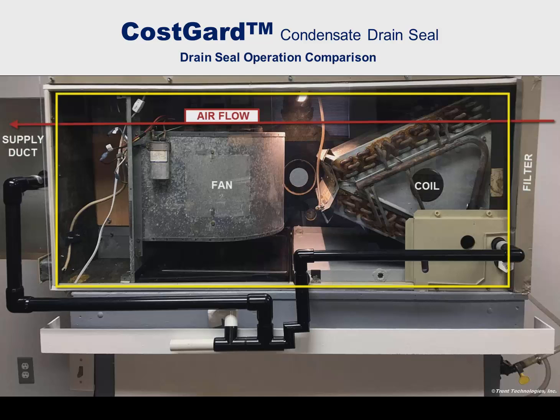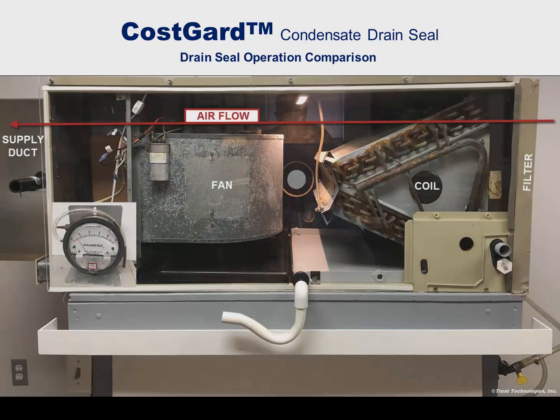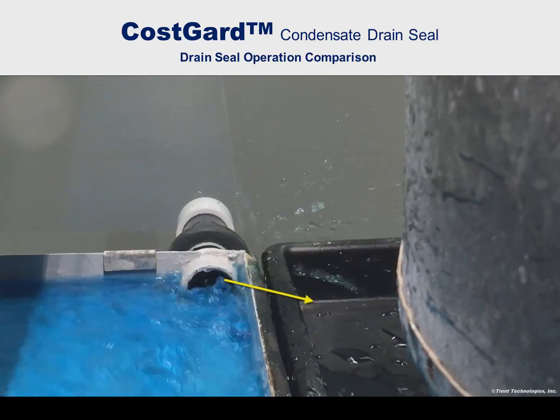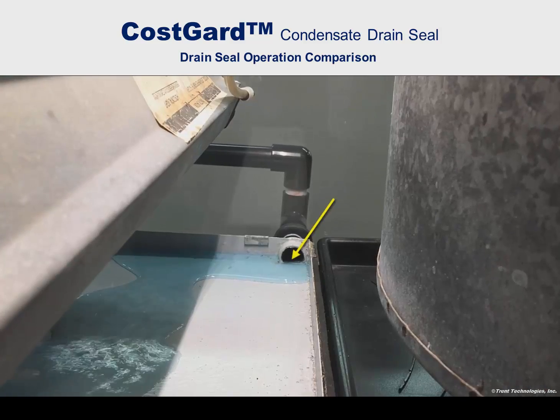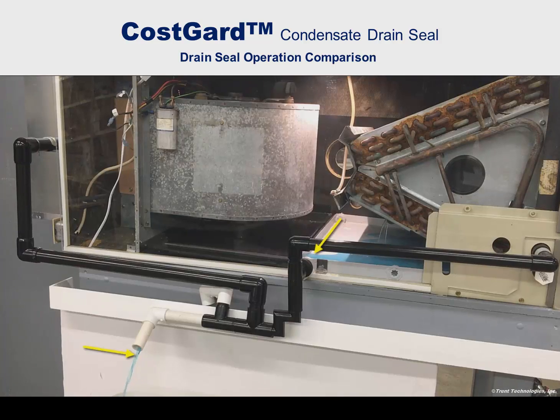With the aid of front and rear transparent panels, the effectiveness of the CostGard condensate drain seal system in preventing the blowing of condensate in a small fan coil unit operating at negative 0.6 inches of water column versus a trap is shown here. See the ingestion of air through the empty trap as the drain pan fills and the blowing of condensate from the drain port back into the unit. Now, with the CostGard condensate drain seal system, note that there is no condensate blowing and condensate flows smoothly through the device.